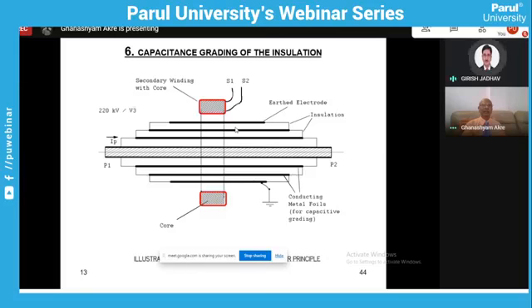Okay. This is how the insulated hairpin primary looks, and after assembly, this is the current transformer. Here, this is a dead tank core where all these cores are mounted. The primary comes from P1 to P2 at the bottom and then goes as a return conductor, P2, P1, P2. There is an insulator between the earth potential and the top potential. This is essential because the transformer lies in the atmosphere, with rains and all this, which is why this external insulation is different from the internal insulation. Internal insulation we have seen, but the external also has to be insulated properly.